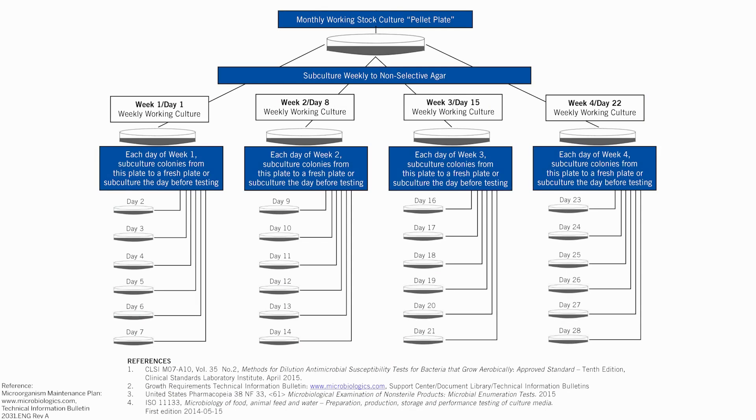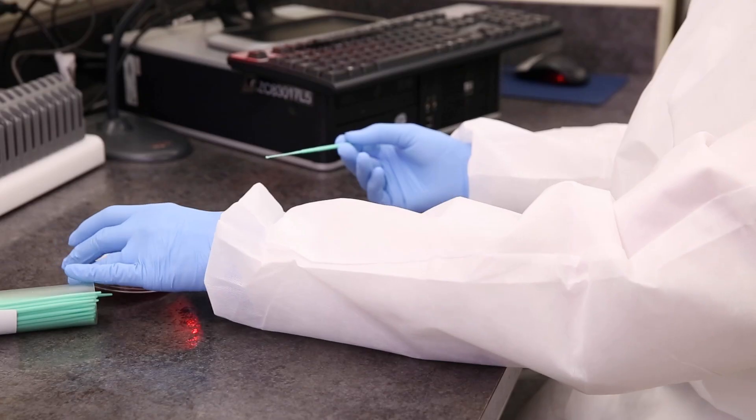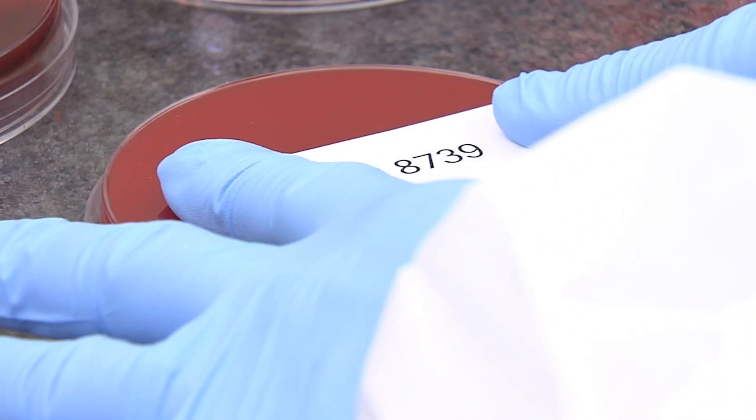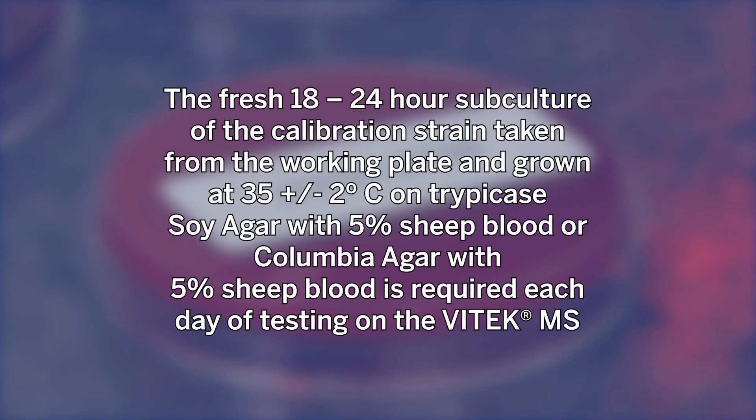After incubation, the stock plate is stored at 2 to 8 degrees Celsius and is used to sub a weekly working culture plate to trypticase soy agar with 5% sheep blood or Columbia agar with 5% sheep blood. This working plate is incubated for 18 to 24 hours at 35 plus or minus 2 degrees Celsius, after which it is stored at 2 to 8 degrees Celsius. The working plate serves two purposes: it is used to make the calibrator spot for the first day post incubation, and it is used to subculture new calibrator plates for days 2 through 7. A fresh 18 to 24 hour subculture of the calibration strain on trypticase soy agar with 5% sheep blood or Columbia agar with 5% sheep blood is required each day of testing on the VITEK MS.